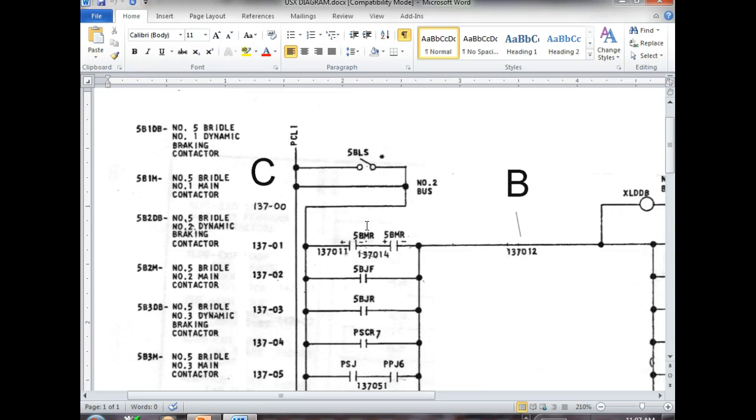But our control circuit, if we call that L1 and L2, and this happens all the time, people are trying to hook up L1 and L2 and they'll take that L1, L2 off the 208 and bring it over into the control circuit without going through a transformer. So normally industry is going to use variations of L1 and L2, right? Just to let you know that it's not that 3-phase L1 and L2 up there. Oh yeah, it happens all the time in motor control.